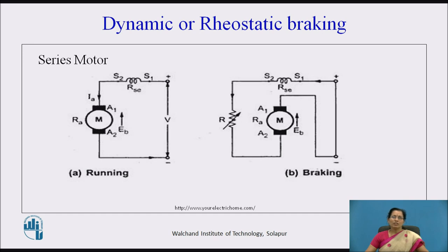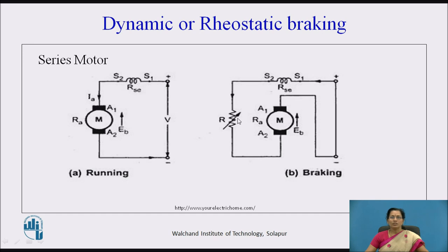Now let us discuss dynamic or rheostatic braking for a series motor. The current direction is downward; the supply voltage is disconnected and a resistance is connected. For rheostatic or dynamic braking of a series motor, we reverse the connections of the armature winding or field winding so that the direction of the current through the series motor is reversed and the torque on the motor is reversed. A1 is connected to the negative and A2 is connected to the positive through a variable resistance, so the opposite torque is created and the motor tries to stop.